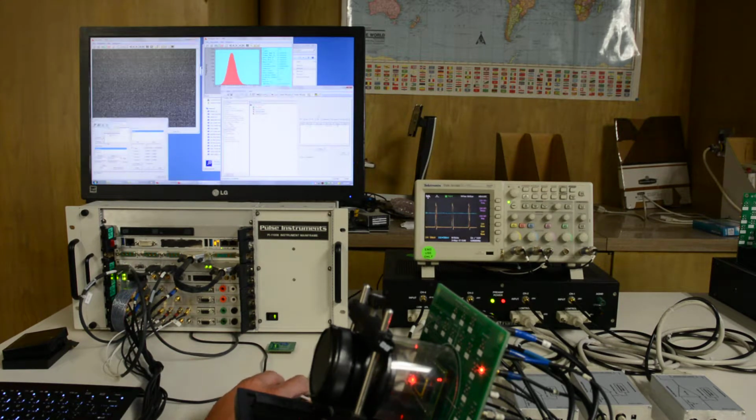I'm going to skip using the programmable black body because I have a slightly faster way to do a quick demonstration. I will select the detector test and calibration test plan. This also presents dialog boxes where I can input the wafer number, die number, serial number, etc., and the pixel area. The second dialog box asks how I want to test the part. I can choose to test offline using previously acquired data, or online using data that I'll acquire now.